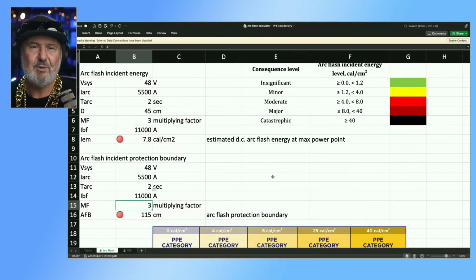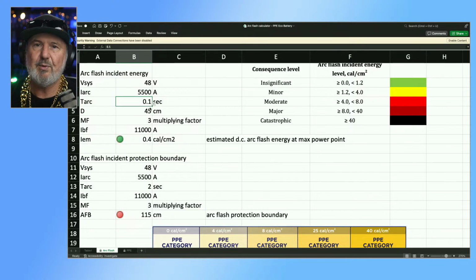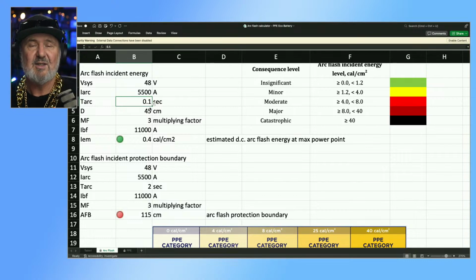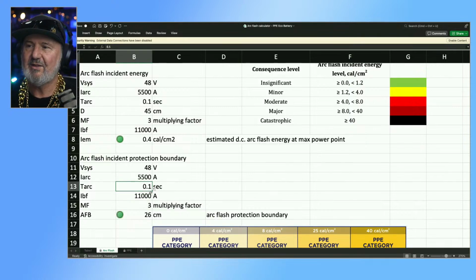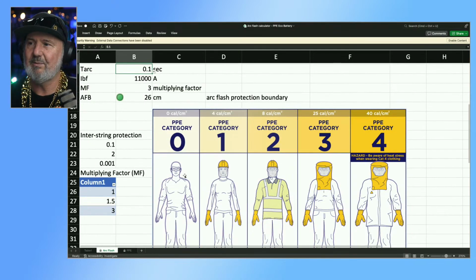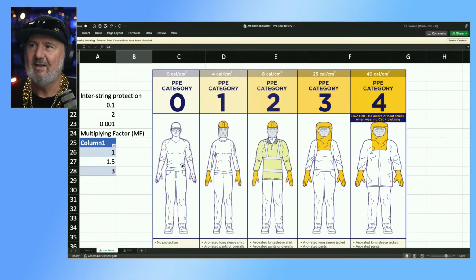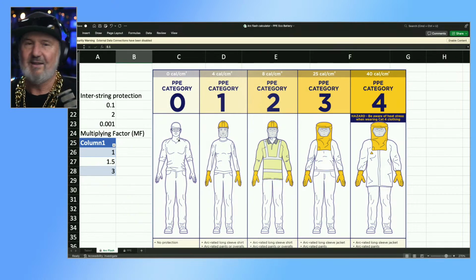So in the midpoint, between the 12th and 13th cell, we put an inline fuse. And that fuse means that the arcing time can be considered to be 0.1 of a second or less if you've got the time current series for that fuse. And look what's happened. Suddenly we've gone from 7.8 cal to 0.4 cal, green light. Green means insignificant. So it's gone from wearing a lot of PPE to insignificant. And so the boundary, well, if it's insignificant, we probably just need a pair of safety glasses. I know it says no protection, but safety glasses are always a good thing to have when there's stuff that can go bang.